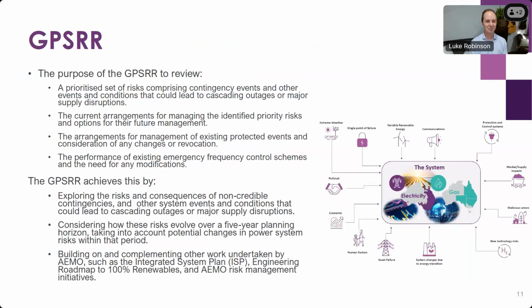Next slide, thanks, Dan. The purpose of the risk review is to evaluate a prioritised set of risks, which comprise contingency events and other events and conditions that could lead to cascading outages or major disruptions to the power system, to evaluate current arrangements for managing the identified priority risks and the options for future management of those events, the arrangements for management of existing protected events and consideration of changes or revocation of those events, and the performance of existing emergency frequency control schemes and the need for modifications.